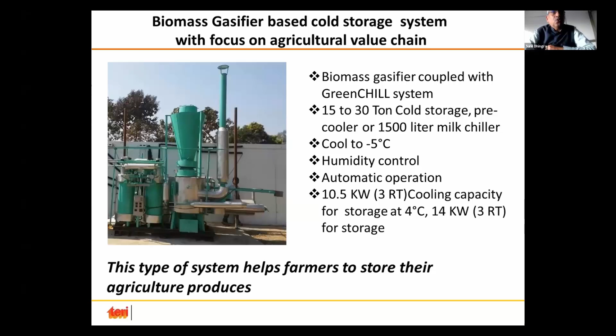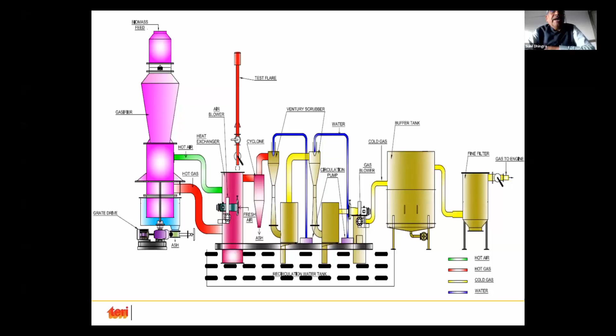On the power generation side, as I told you, biomass gasifiers produce some impurities in the form of tar and particulates, which need to be cleaned, and the gas must be cooled before being fed into a gas engine commonly used for power generation. This is the scheme of cooling and cleaning system adopted by many gasifier suppliers and manufacturers. Typically, for power generation, these are downdraft gasifier designs, again fixed bed.